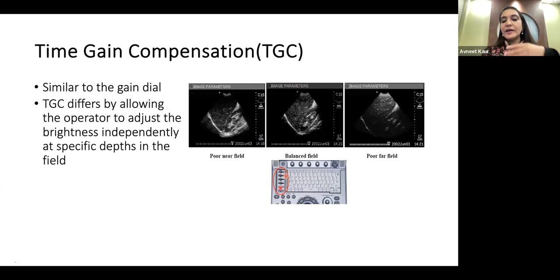Now, a very, very important element, which is the depth. If I have to choose one parameter to adjust my image, first and foremost it will be my depth. So what do we understand by depth? Depth means that the image depth should be set so that the desired structure falls at least in the center of our image, or occupies at least 2/3 of the acquired image.